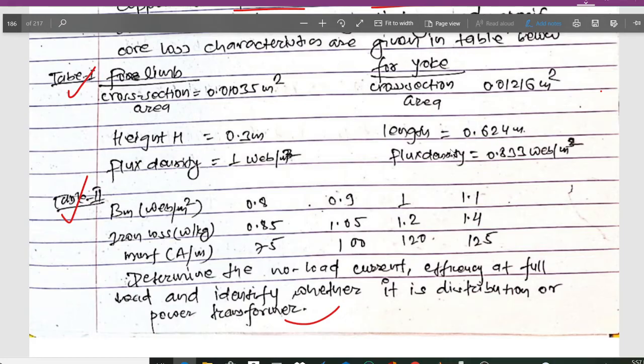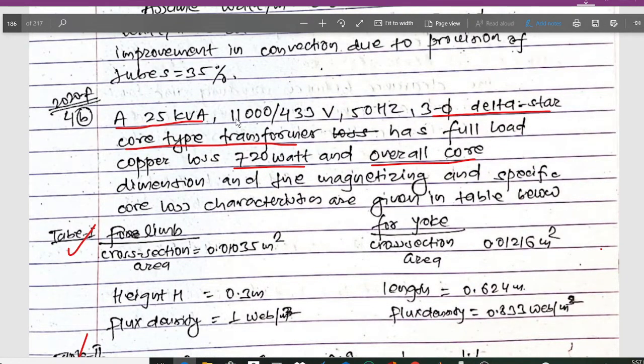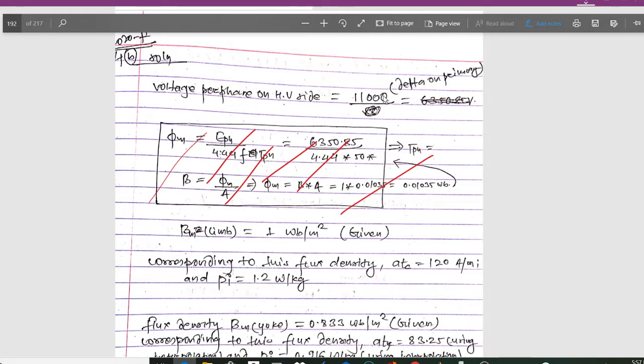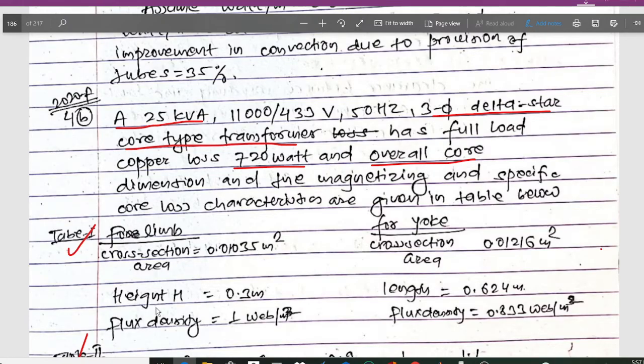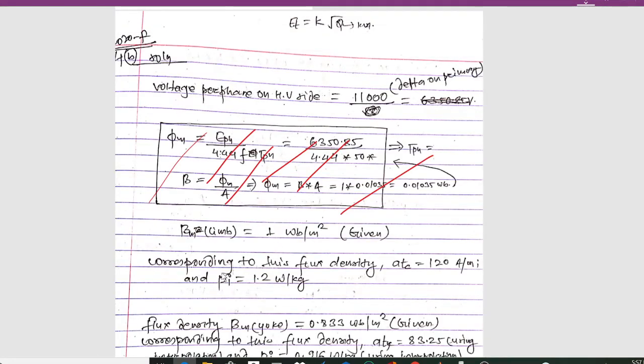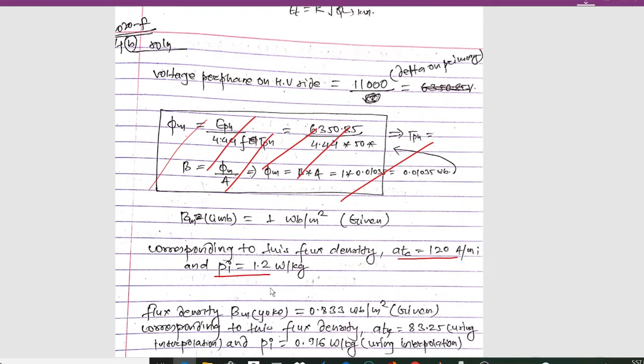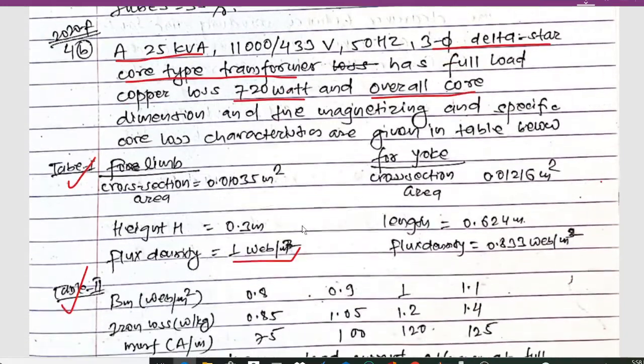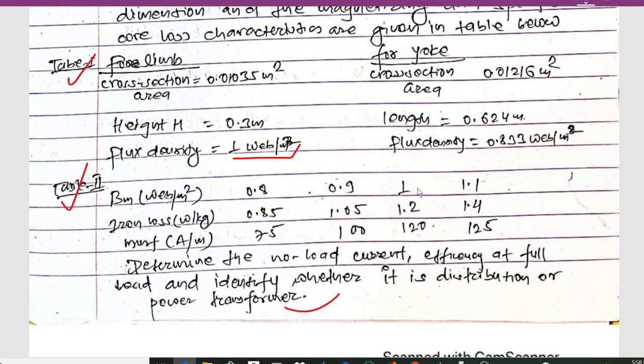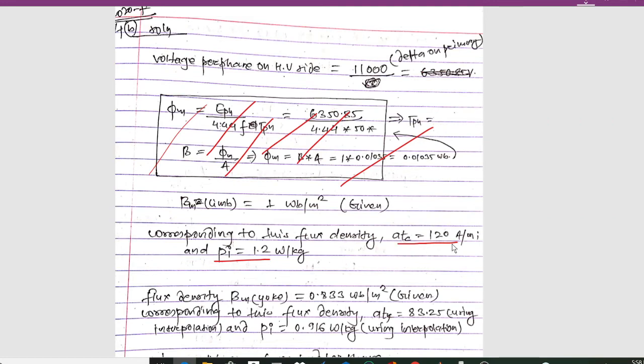Since this is a delta-star transformer, the high voltage side is 11,000 V, so the voltage per phase on the high voltage side is directly 11,000 V. Now BM is given as 1 weber per meter square for the limb. Corresponding to this flux density, ATc is given as 120 ampere per meter and Pi is given as 1.2 watt per kg, taken from Table 2.